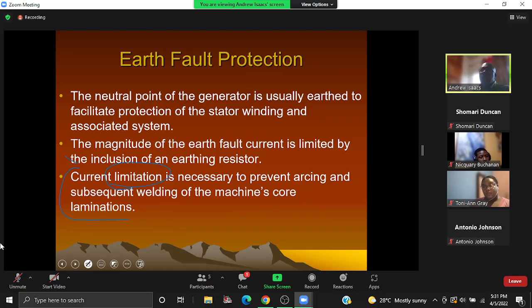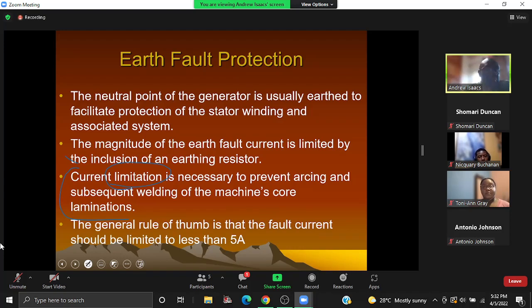You with me? So I'm putting in the earthing resistor because I want to limit the amount of current. But if I put in the earthing resistor and limit the amount of current, it is reducing the responsiveness of the protection system, because I want as large a current going to the protection so the protection will operate quickly. So part of the discussions this afternoon, this evening, is about how do we treat with that? How do we ensure that we can mitigate against that? Not sure that still obtains, but anyway, we try to limit it to about 5 amperes. Don't write that down and take it as gospel.